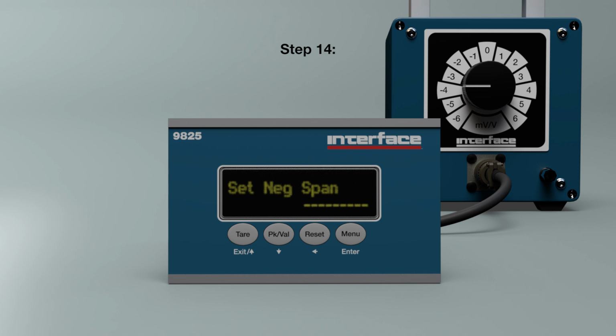Step 14. Once the 9825 has finished recording the NC1 value, NC2 will be displayed. For this example, we will only be using one cal point on the negative span. Leave the NC2 value set to 000000 and press the menu key to exit. The Set Negative Span menu item will be displayed.